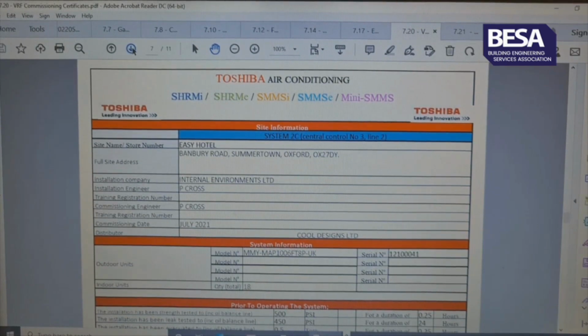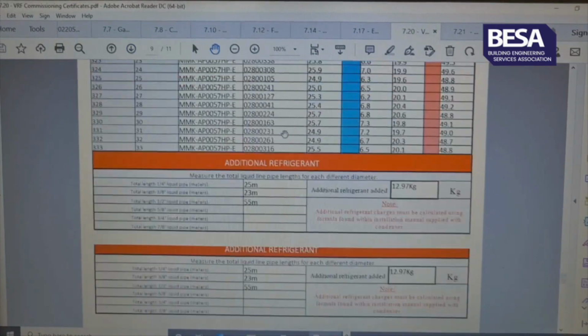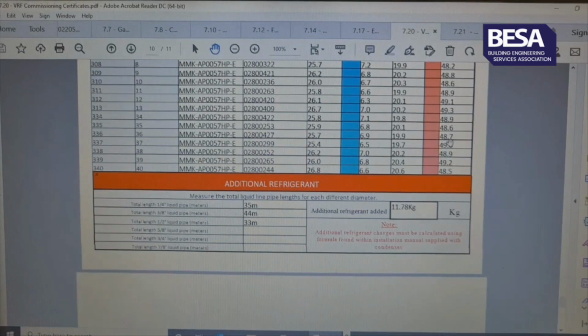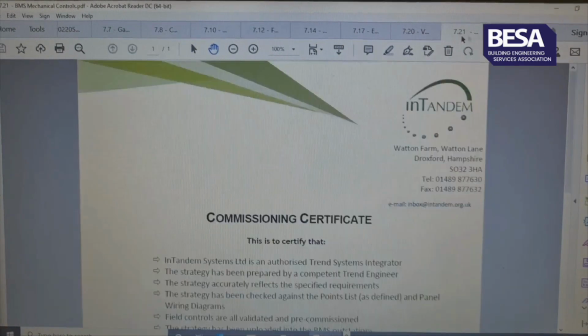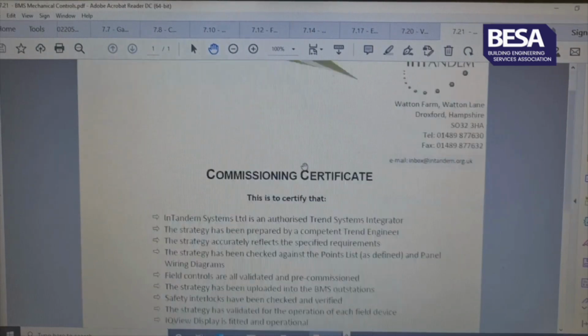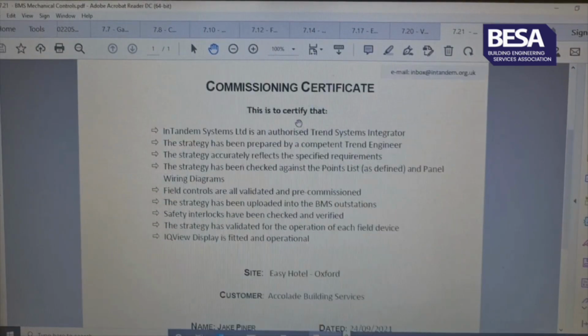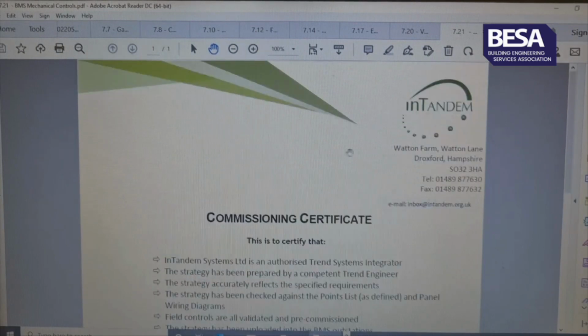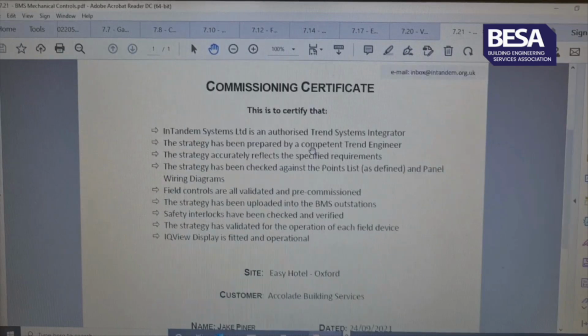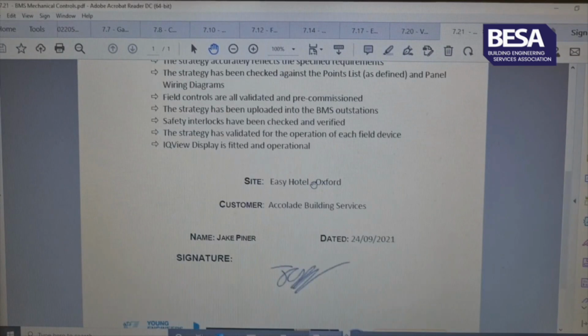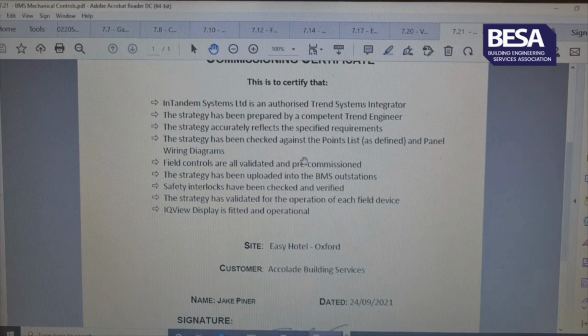Got to scroll down. They don't look like they're changing, but they are as I scroll. So that's all signed off. And the next certificate, which I think is the last one I'm going to show you, is the BMS. So this is a commission certificate to prove that the BMS company called In Tandem carried this out for us, one of our subcontractors, to verify that the BMS has been fully commissioned. So this is the Trend system that we saw, the controller in the plant room in the main control panel.